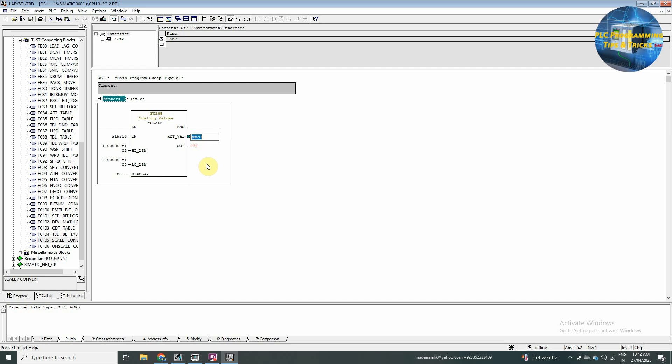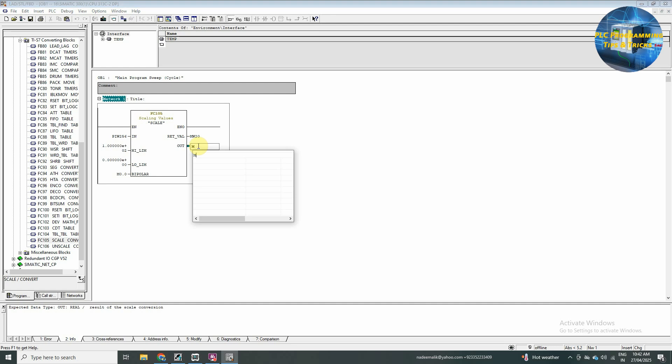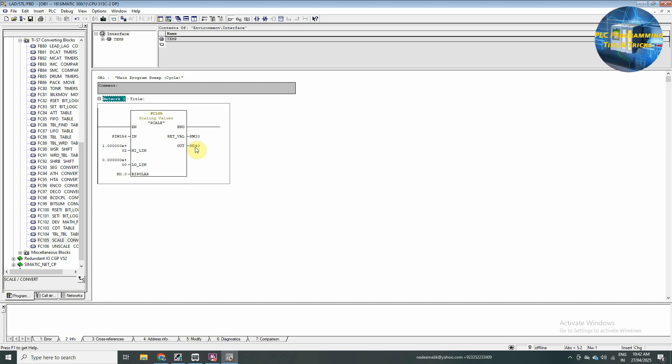So, it will show any error information in the memory word MW 20. And the scale value will be our output. And we will insert here MD 24. So, this is a double word MD 24, and we will carry the scale value to 100% in it.